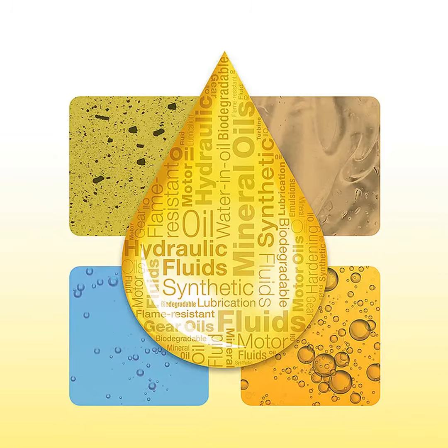Once a machine begins operating, contamination doesn't stop. In fact, the machine starts producing contamination of its own. Normal wear creates particles as components interact with each other. Those wear particles then create more wear. It's a cycle where contamination generates additional contamination. The lubricant itself also changes over time.